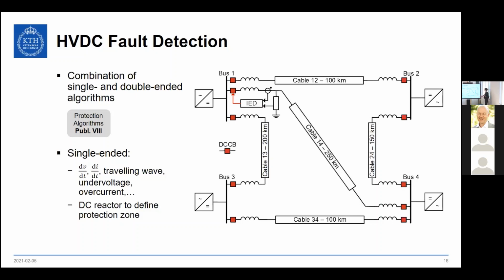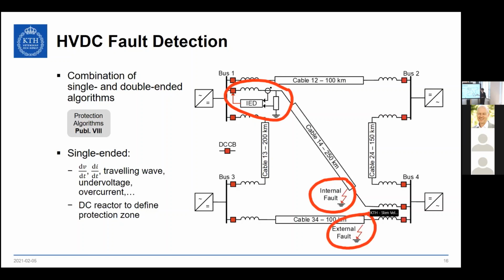Now, one important aspect for the single-ended line detection is the DC reactor to define the protection zone. And I'm going to explain what this means with an example again. So if we take this internal fault here, then the measurement and fault detection up here has to be able to distinguish this internal fault from an external fault, because for an external fault it's not supposed to detect it or trip, and the only electrical differences in between are these line inductors. So the sizing of those becomes important for shaping the actual physical signals that are then fed into the fault detection. And I'm going to come back to that line inductor sizing later.